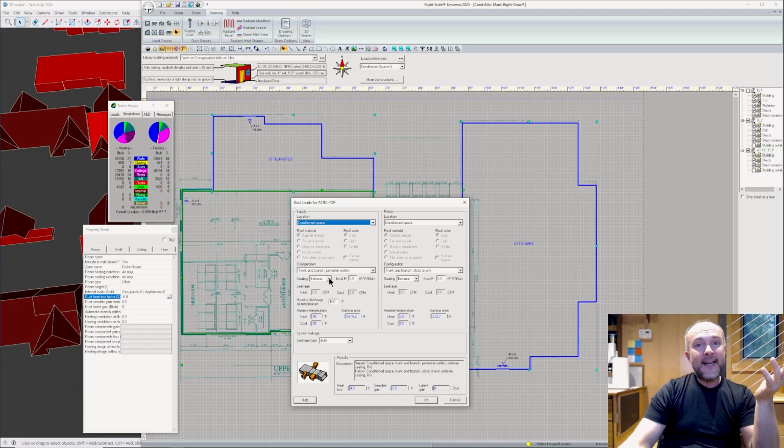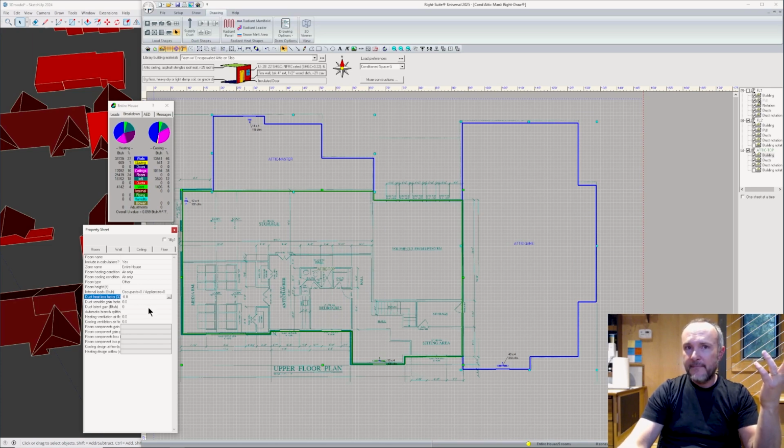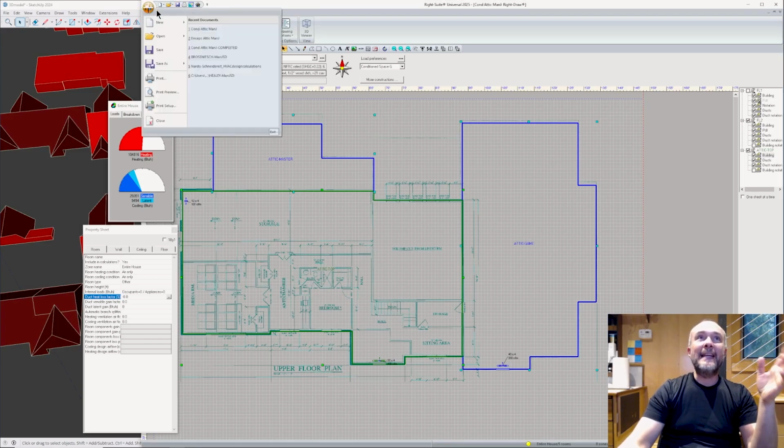But if we mess that up and they don't get sealed, you won't find out in an encapsulated attic. In a conditioned attic, if we go completely unsealed with these, we could see that we've changed nothing. I have no extra load that gets added as a result of that. So I'm still locked in at 105,000 heating and 38,500 cooling. Now flipping back over to the encapsulated attic.